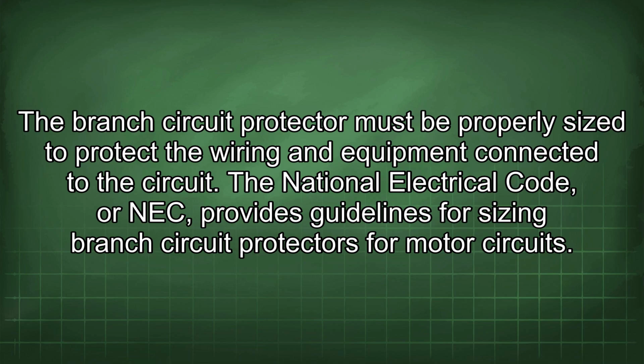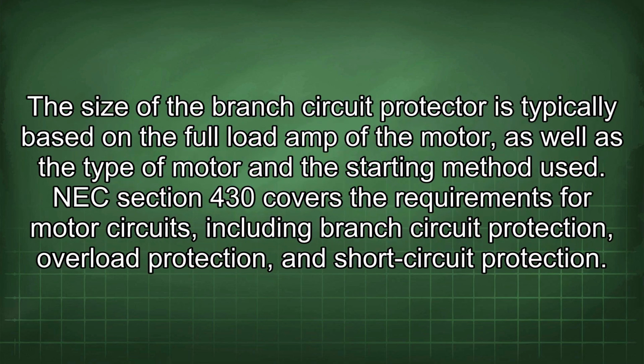The National Electrical Code, or NEC, provides guidelines for sizing branch circuit protectors for motor circuits. The size of the branch circuit protector is typically based on the full load amp of the motor, as well as the type of motor and the starting method used. NEC Section 430 covers the requirements for motor circuits, including branch circuit protection, overload protection, and short circuit protection.